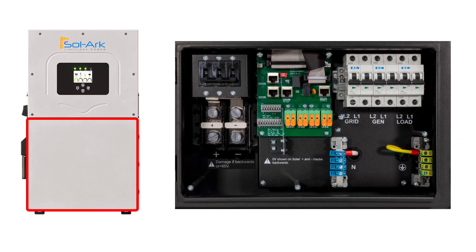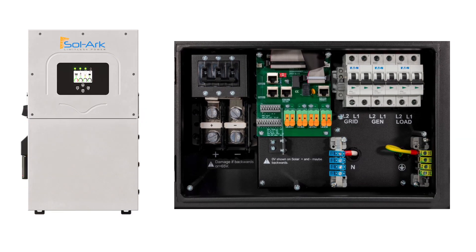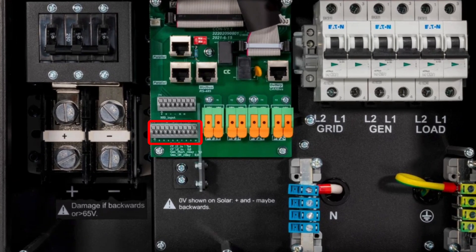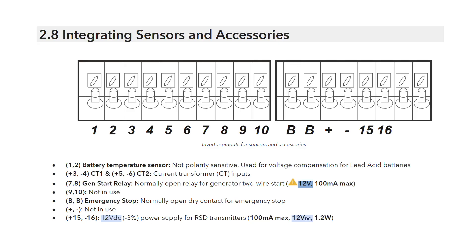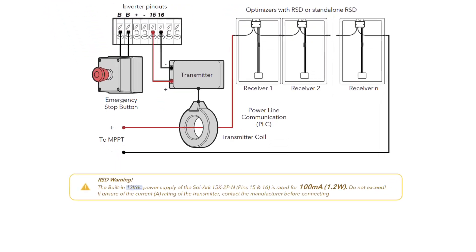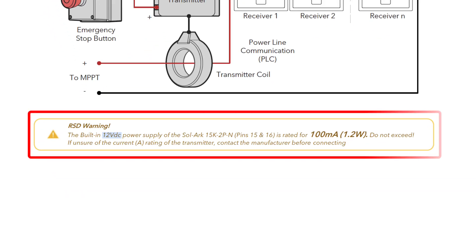Solark hybrid inverters have an internal 12-volt pin pair for external rapid shutdown transmitters. These pins are marked 15 and 16. The manual states the output of the 12-volt pins is 100 milliamps, and that you should check with the rapid shutdown transmitter manufacturer for questions about the power output.